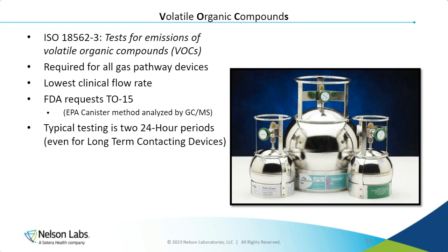We are left with an extensive list of quantitative compounds and semi-quantitative compounds. The length of time for this VOC sampling should be multiple 24-hour periods. It is typical for sampling to occur in 2 separate 24-hour periods, even for long-term devices. This gives us 2 days worth of data, the first 24 hours and the second 24 hours, 24 to 48.